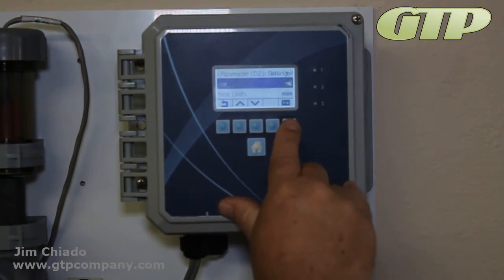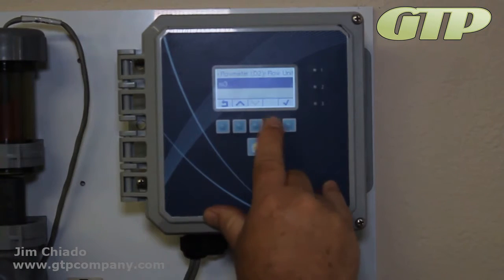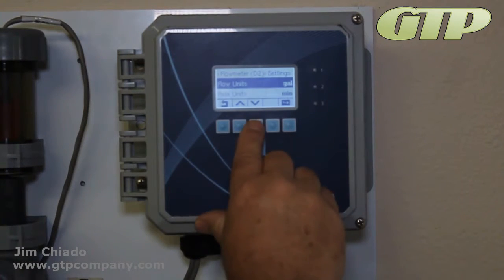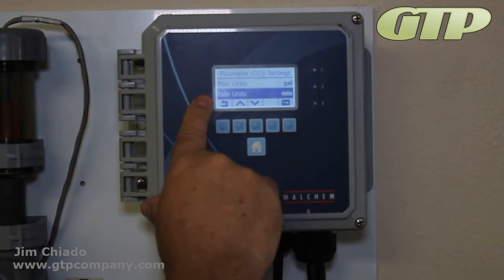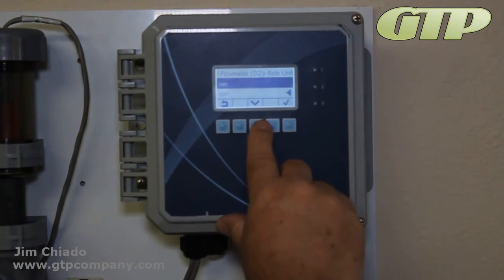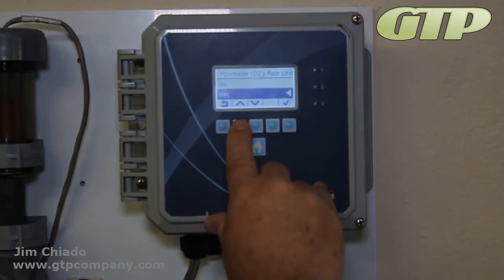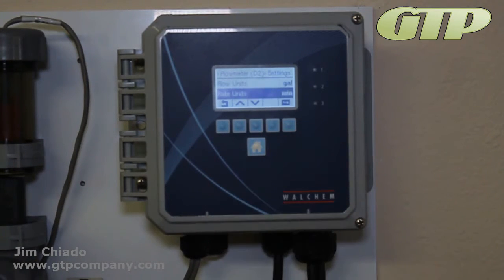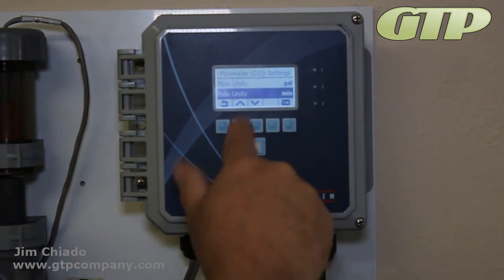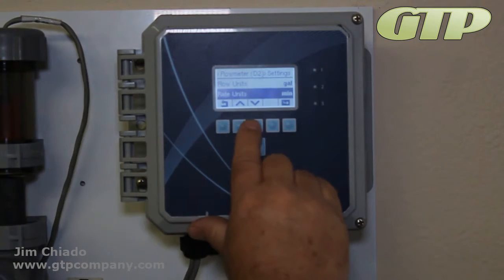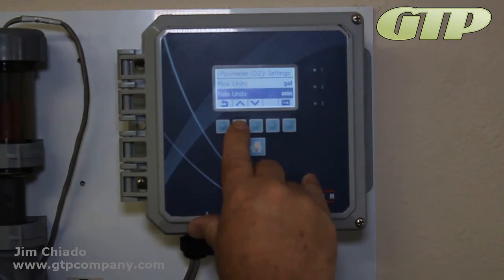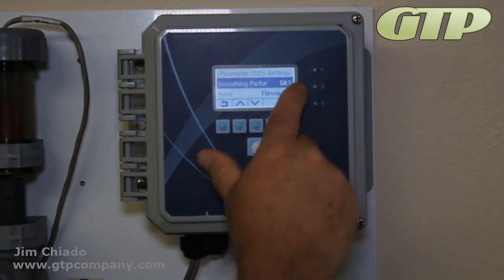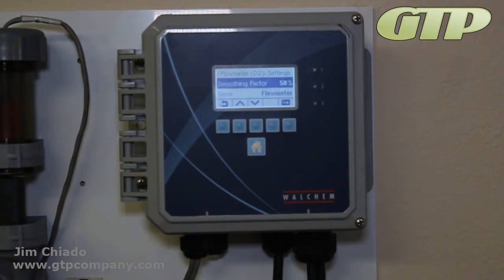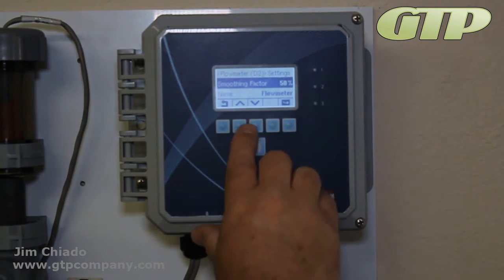Flow units, right now gallons, you can make it say liters and cubic meters. Rate units, right now it says minutes, hours, days. You can make it say a lot of different things, but we want gallons per minute, gallons per hour, gallons per day. We wanted to say gallons per minute, what most people understand. Smoothing factor 50%, it does smooth it out for you because it does jump around a bit.